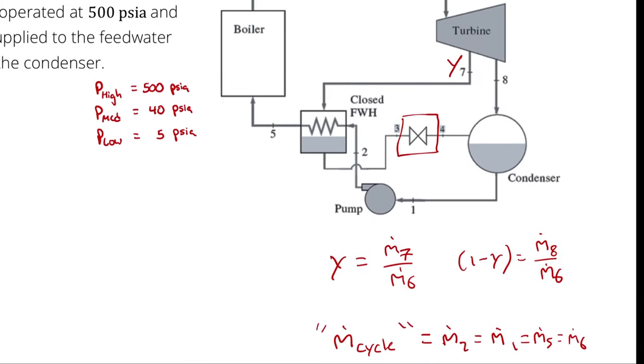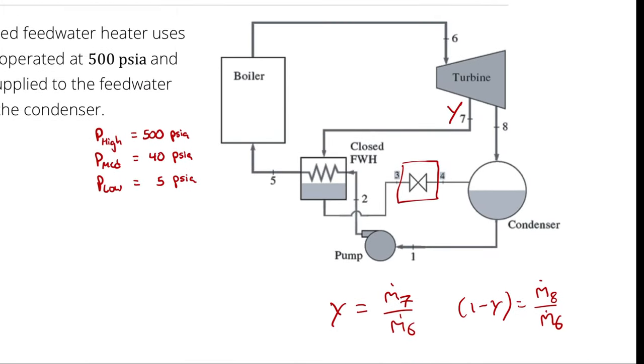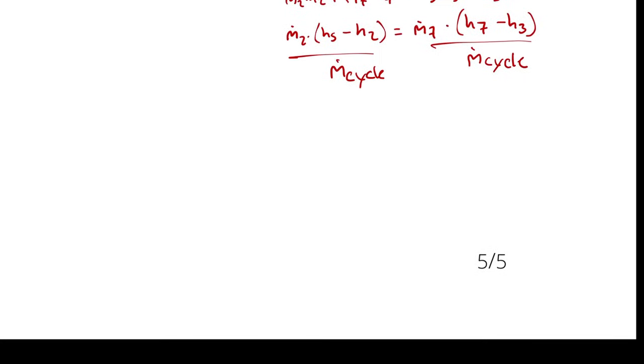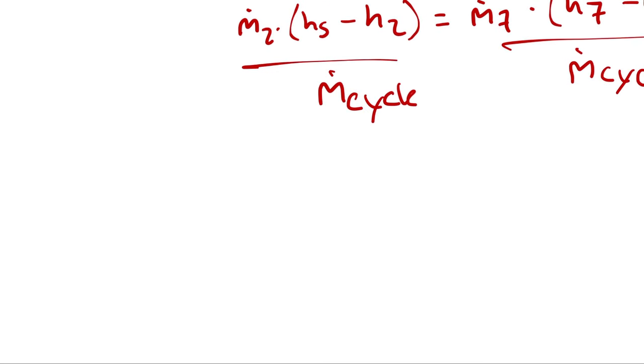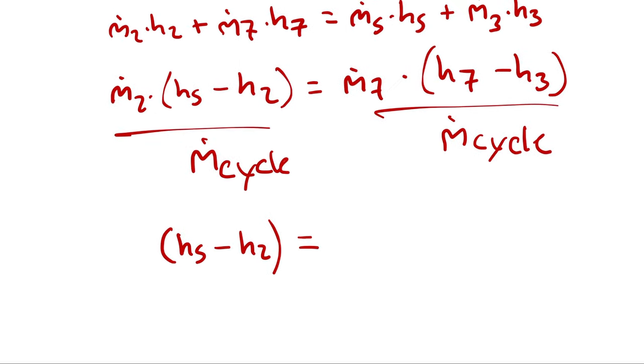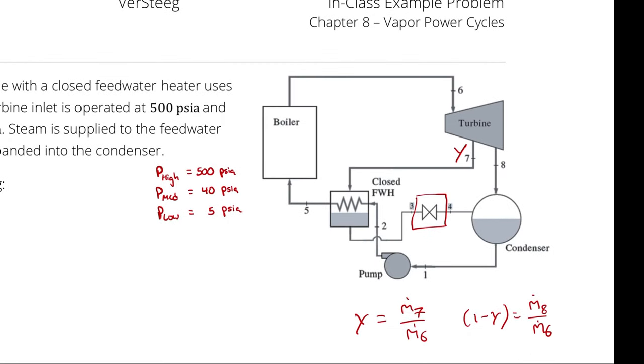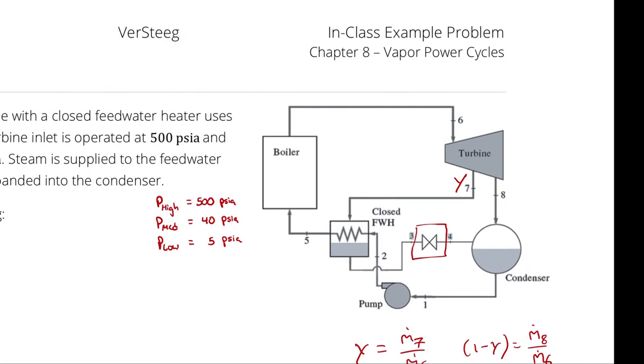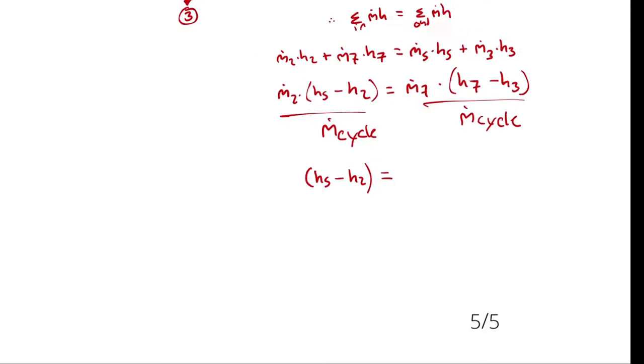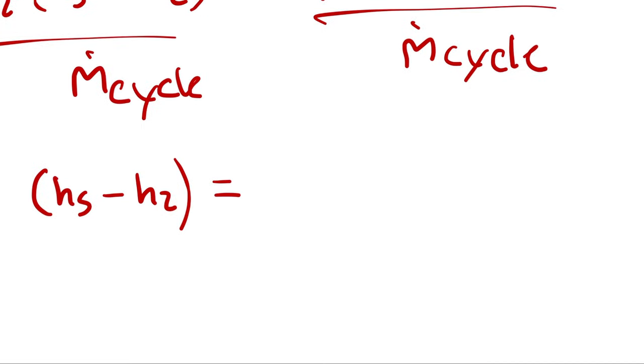m.2 divided by m.cycle is 1, because m.2 is equal to m.6, and m.cycle and m.6 are the same. So note here that if you had just copied over the energy balance on the closed feedwater heater, complete with all of the algebra below it, from the previous problem, you would have an incorrect answer because the mass flow rates are different.